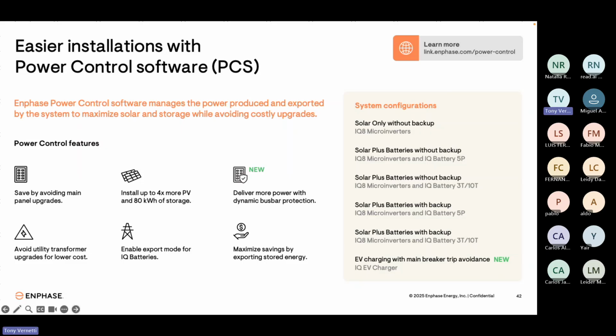One thing that makes Enphase systems able to be installed on most electrical panels is what we call power control software, or PCS for short. PCS is a way of controlling the amount of electricity flowing through the system, and depending on the building department or authority having jurisdiction's requirements, we can usually install Enphase systems on electrical panels of homes that might otherwise be very limited.